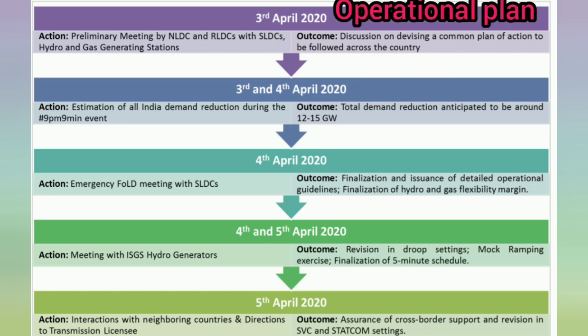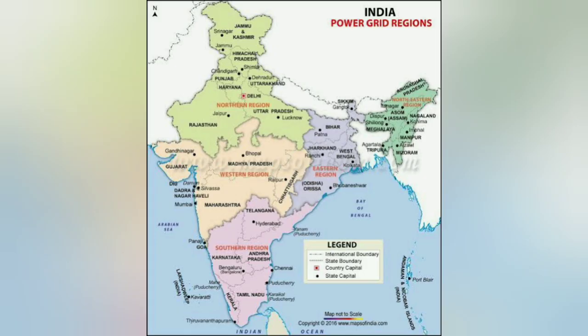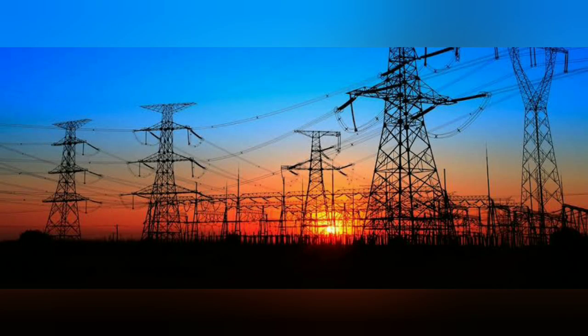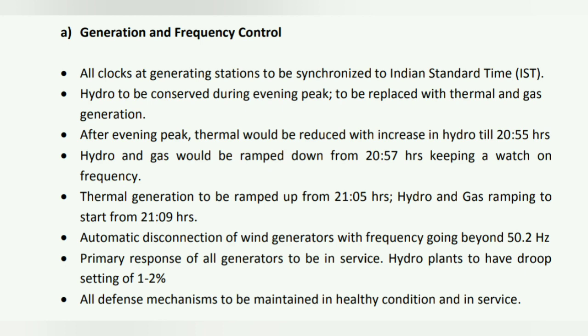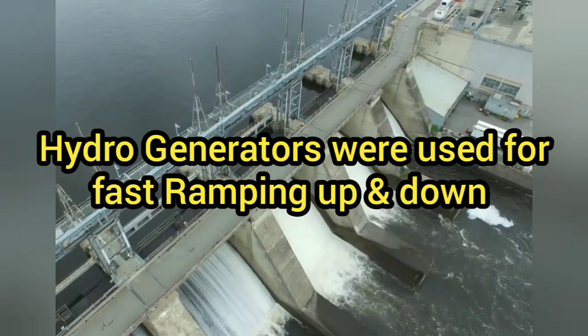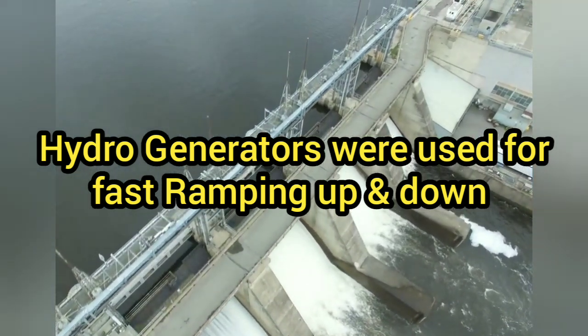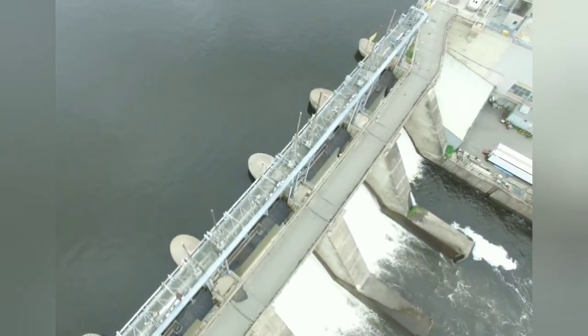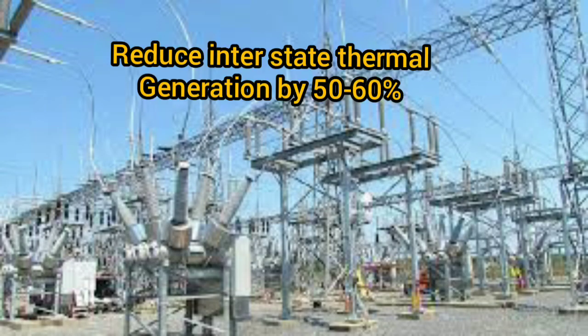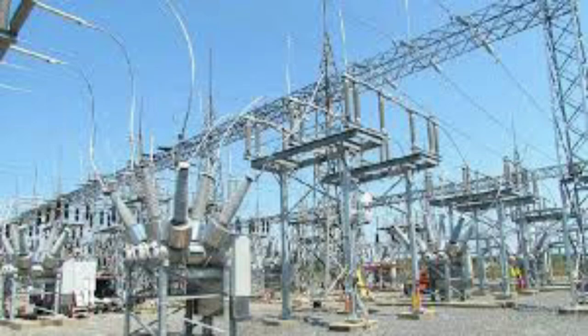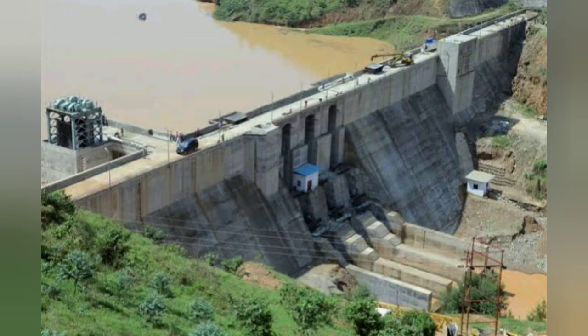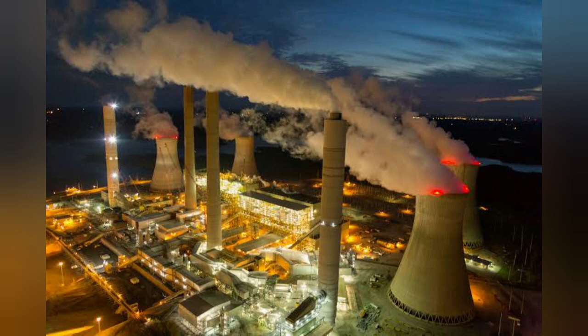They made an operational plan for successfully managing the 9 p.m. 9-minute event. They ensured load generation balance at all times during the event for frequency control, ensured voltages are within permissible limits at all nodes, and ensured transmission network loadings within permissible limits along with system stability. So hydropower was used for fast ramping down and ramping up for this event. It was also planned to reduce the scheduled interstate thermal generating stations to near the technical minimum level of 55 to 60% just before the start of this event. It was also planned to ramp down hydro and gas generation fast with the start of the event while keeping a watch on the system frequency.